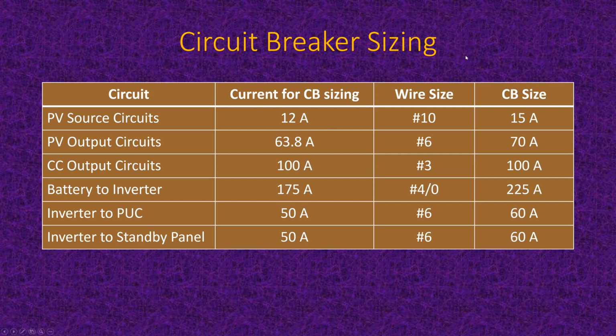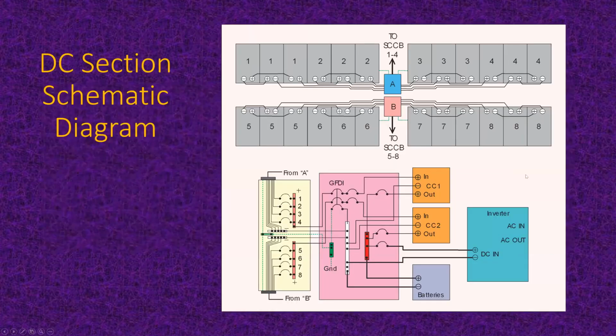So anyway, here's your sizing of the circuit breakers for that 8,000 watt system. And here's your schematic diagram for it, okay? For the DC side. And you can see we've got 8 source circuits, three modules each. Go to those combiner boxes, box A and box B. They then feed this DC control side with ground fault detection now for 2 poles, because we now have 2 charge controllers, a bigger set of batteries, and to the DC input side of the inverter.